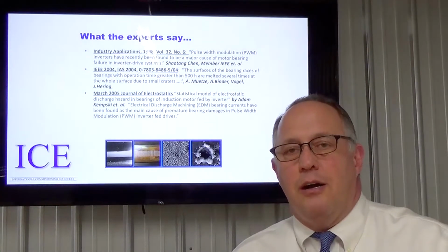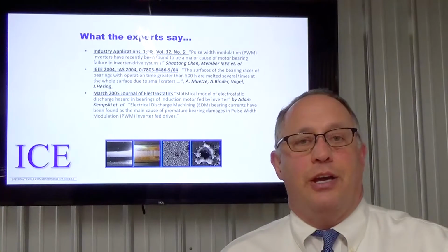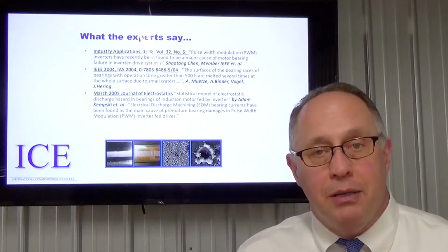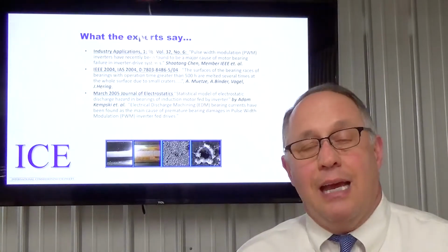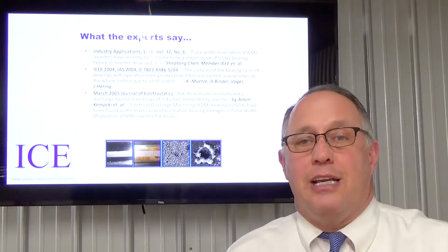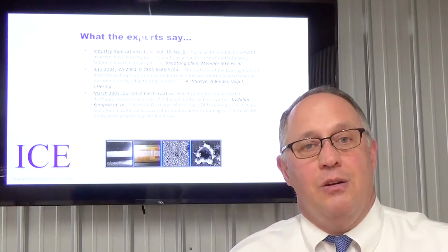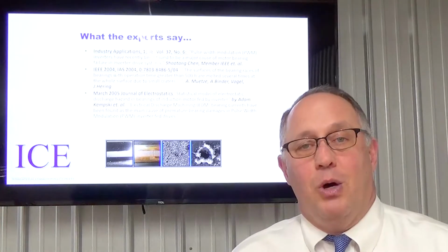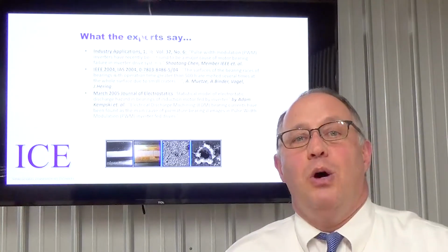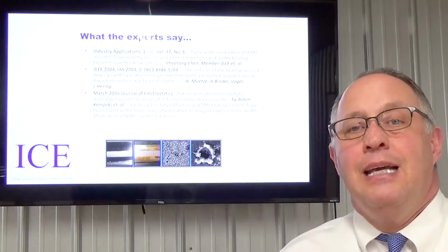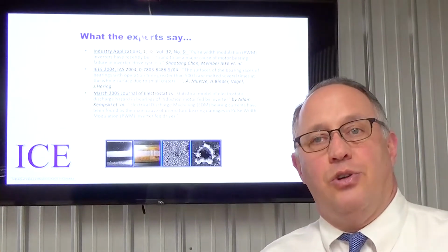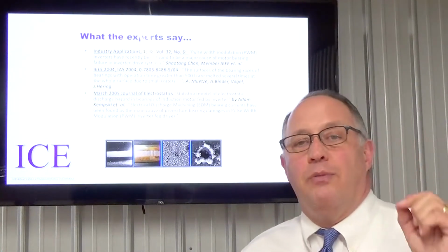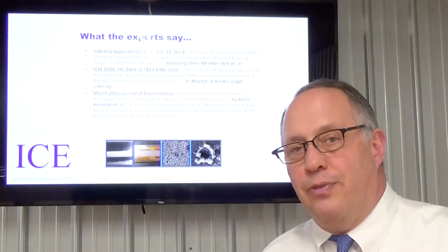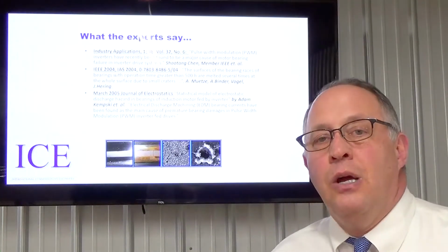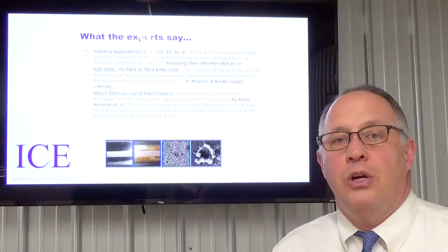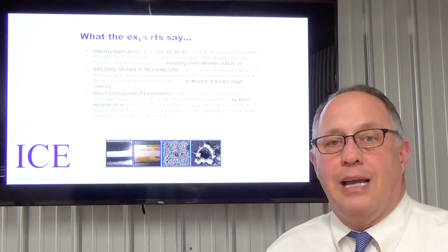Lots of times, maintenance folks just go out there and know that a motor's burned up. That's pretty much the extent. And for that reason, they want to get things back up and going. So they take that motor off, put a new motor in, hit the start button, get it back going, because that's their charge, to keep things going. But if we really look at what caused the failure, and that's what we're talking about today, we'll find that 90% of those are the result of this type of bearing failure.